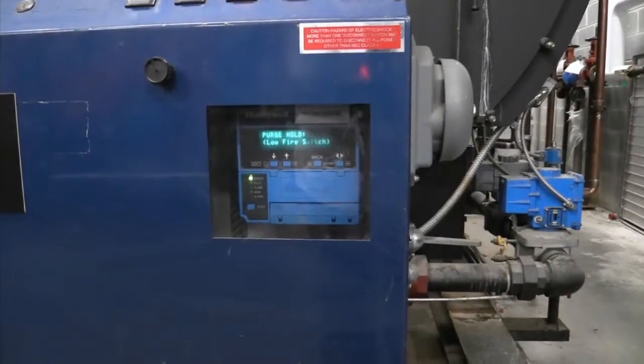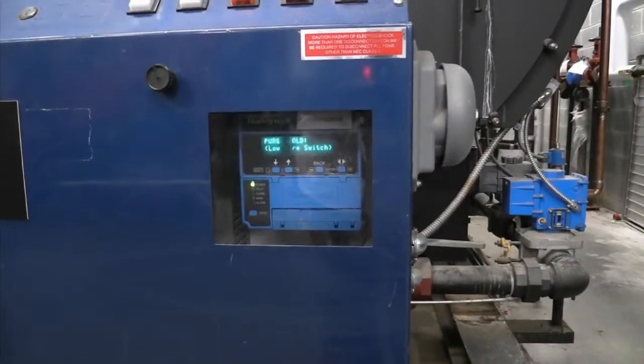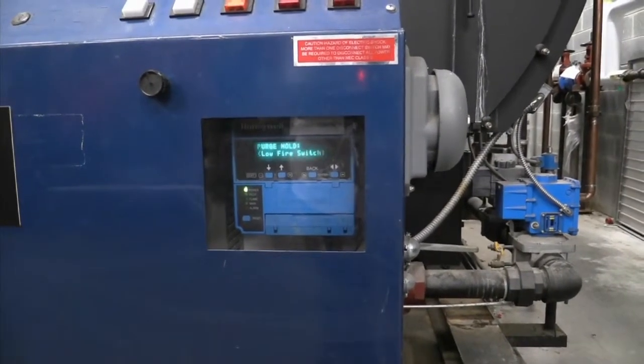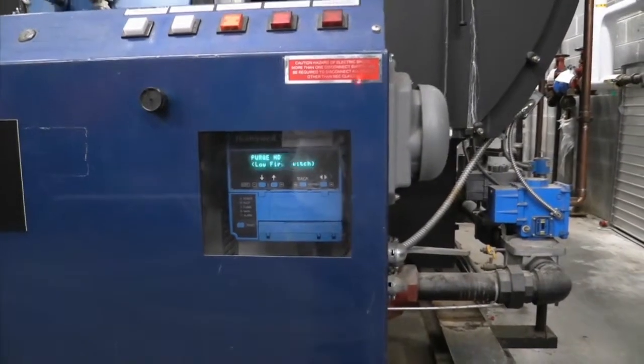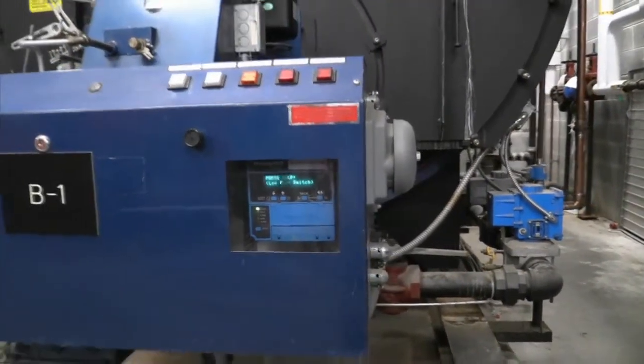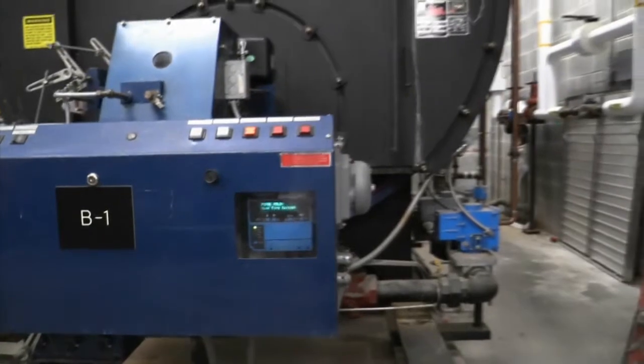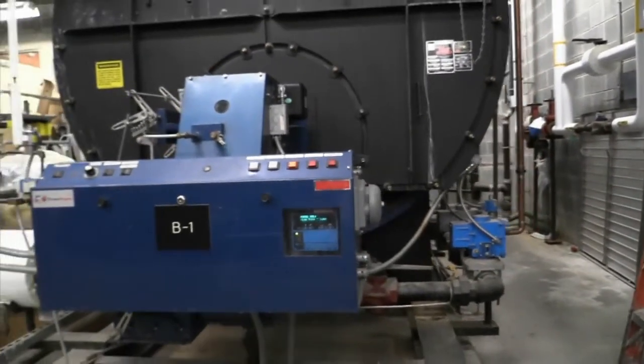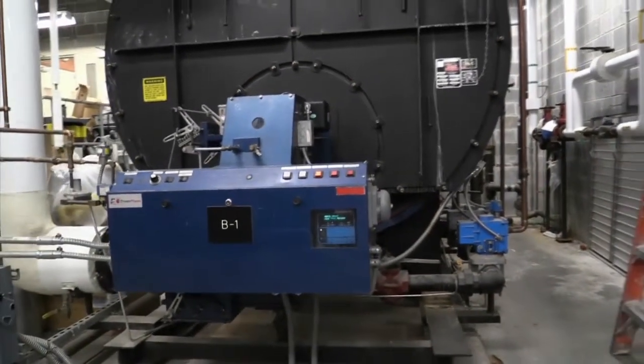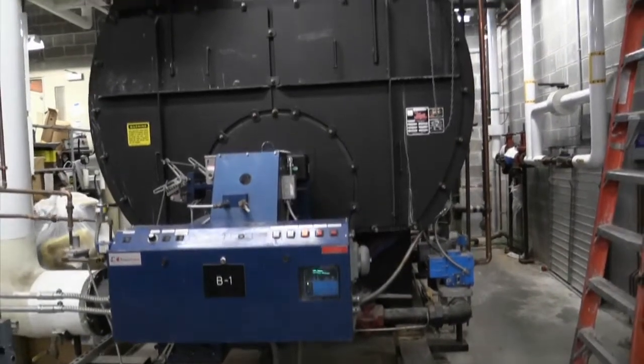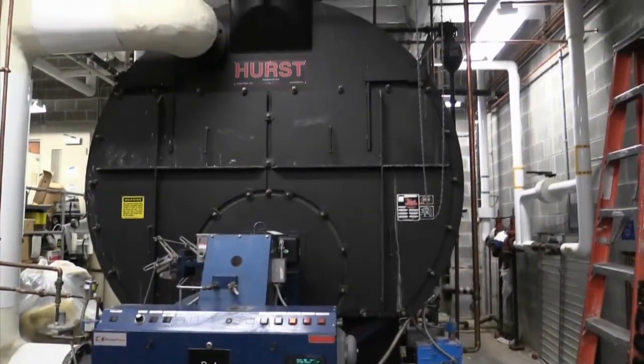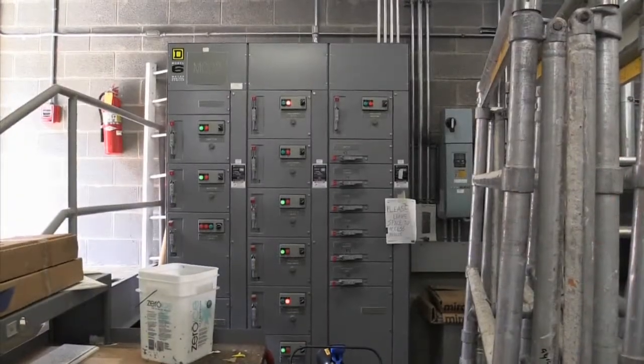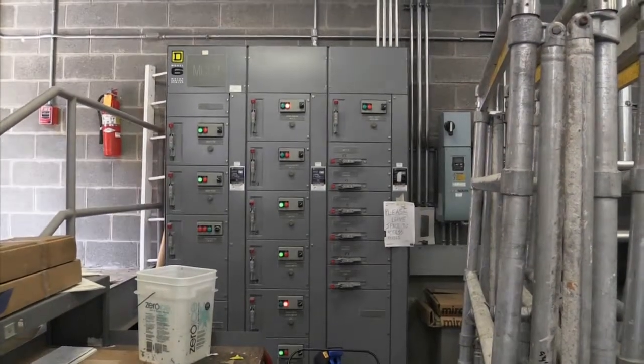The recommended implementation method would be to manually decrease this set point by 2 psi increments over a 1 to 2 week period during warm weather and to monitor for impacts in the building. If no impacts are observed, decrease again and monitor. Stop decreasing at 10 psi set point or until occupant complaints can be directly related to a reduction in the set point.